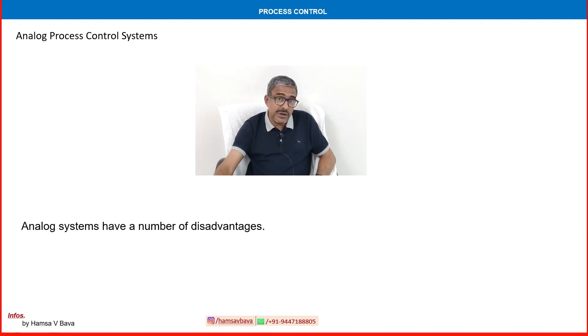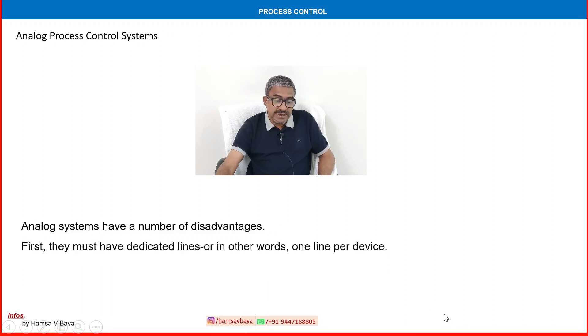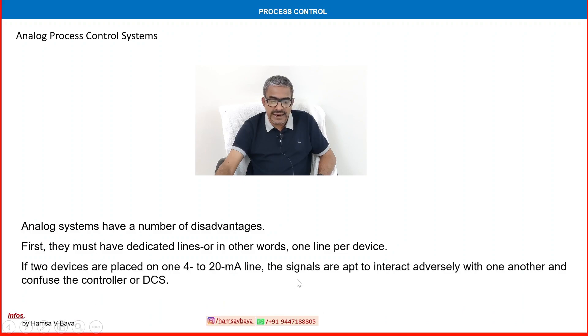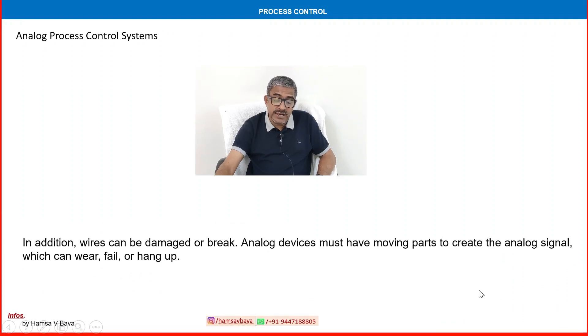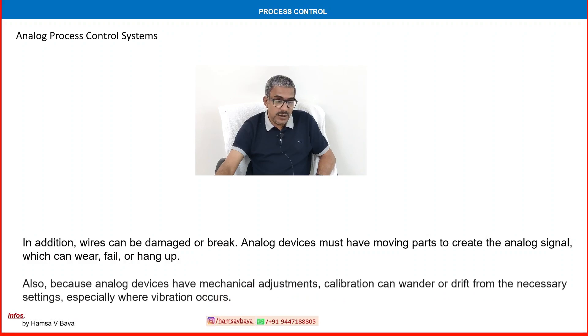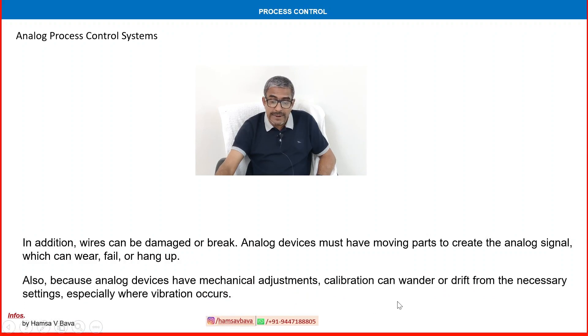Analog systems also have a number of disadvantages. First, they must have a dedicated line — one line per device. If two devices are placed on one 4 to 20 milliamp line, the signals are apt to interact adversely and confuse the controller or DCS. Electrical lines can also be influenced by magnetic fields and radio frequencies, and wires can be damaged or break. Analog devices must have moving parts to create a signal, which can wear, fail, or hang up. Additionally, because analog devices have mechanical equipment, calibration can wander or drift, especially where vibration occurs.